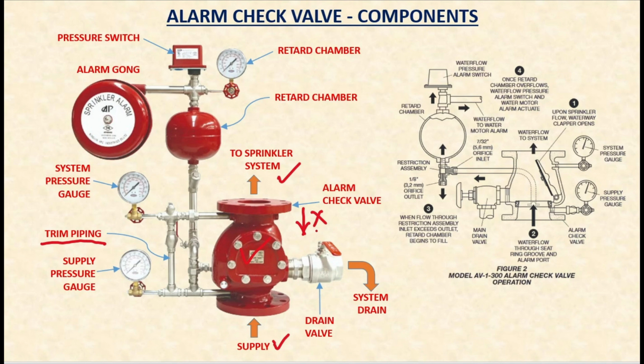Now this happens because it has a hinged disc called a clapper. See this part. This basically is spring actuated. So this clapper allows water to flow into the system when opened, but prevents water from flowing back when closed. When this is closed, water cannot come below. See, water cannot come here. Water cannot come here. It's closed actually.